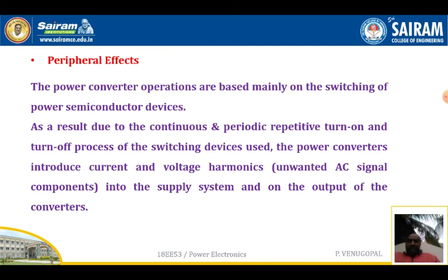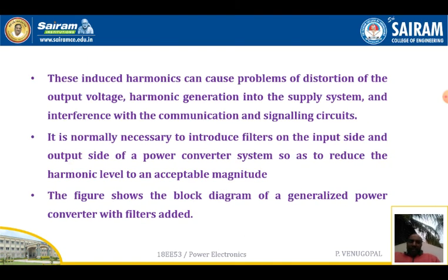We also have devices like MCT and TRIAC. The switching of these devices converts power from one form to another. As a result of the continuous and periodic repetitive turn-on and turn-off process, power converters introduce current and voltage harmonics into the supply system and also into the output of the converters. These induced harmonics can cause problems of distortion of the output voltage, harmonic generation in the supply system, and interference with communication and signaling circuits. It is necessary to introduce filters on both the input and output sides of the power converter system to reduce the harmonic level to an acceptable magnitude.